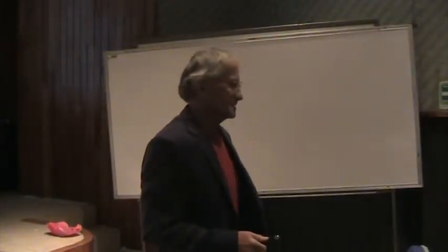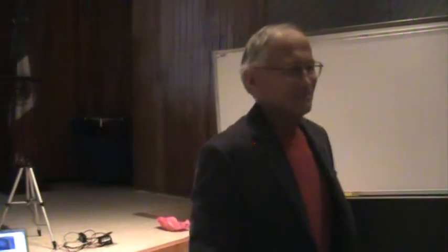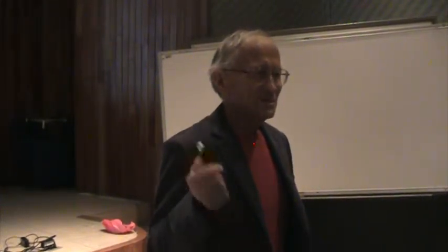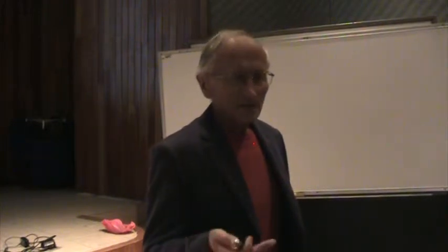Now, next, long-term stability. Let's compare both platinum and thermistors. What do you think? Both short and long-term stability. Early morning is difficult, yeah? Pardon? For platinum, excellent. Excellent short and long-term stability. For thermistors, probably we can obtain short-term stability, not very good, bad, but for long-term stability, we cannot expect good results.